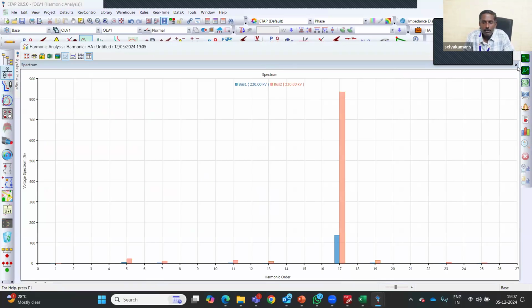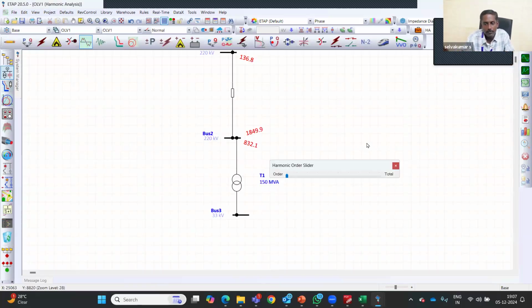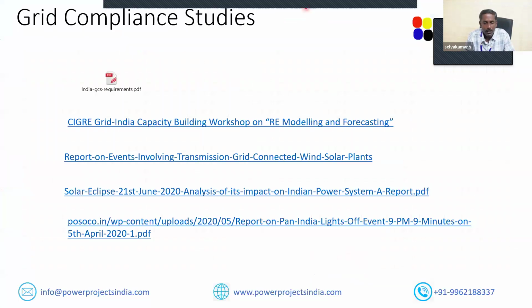This is all something we need to take care of during the design. That's where grid compliance studies or grid connectivity studies come into picture and add a solution. So go to the India grid compliance study requirements: you perform power quality studies, and if the power quality harmonics exceed the limit, recommend necessary filters, or modify the line length, or add parallel circuits—do whatever you want to eliminate the harmonics.